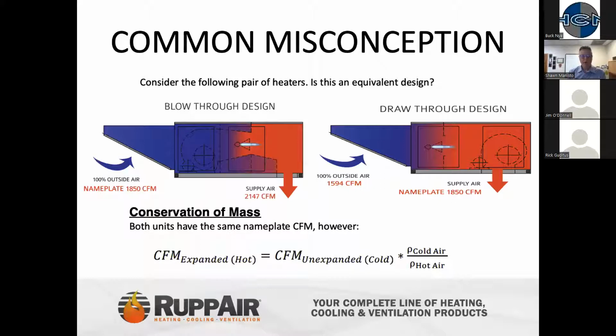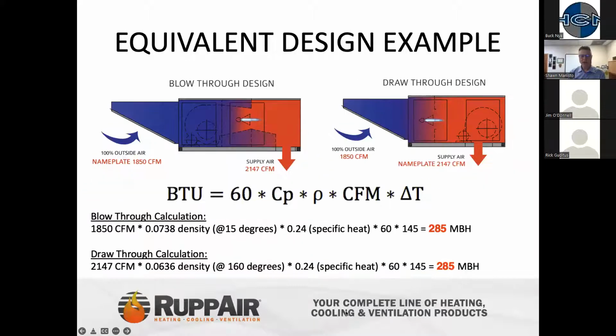One common misconception is also about a draw through or push through style system. This illustration just gives you a snapshot of two different ways of the 100% high temp units that are used for heating warehouses, between a push through style system and a draw through. And the biggest thing to point out is that although CFMs may appear to be different, in the end, they're going to utilize the same amount of CFM to create the BTU capacity to heat this building.